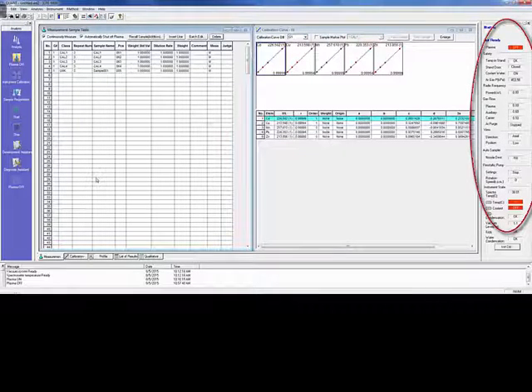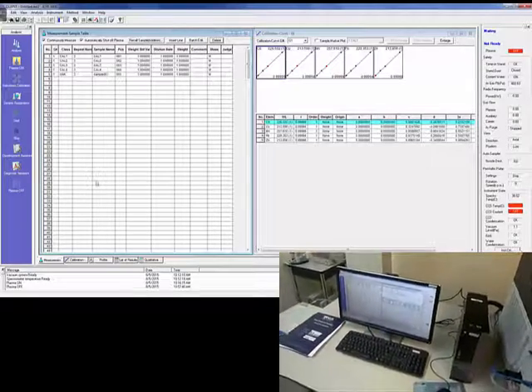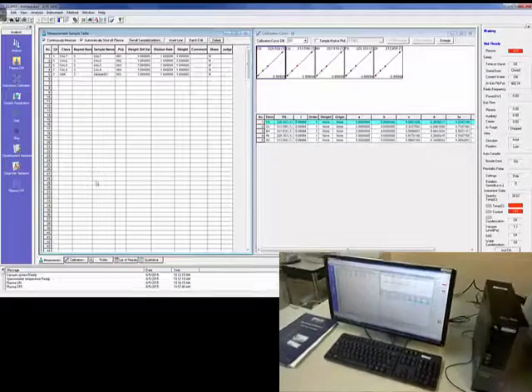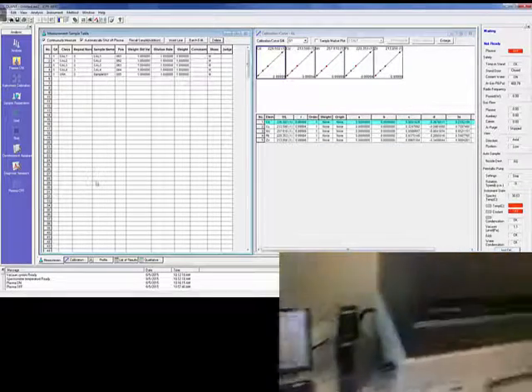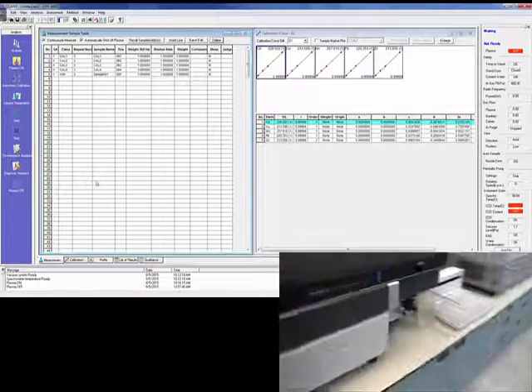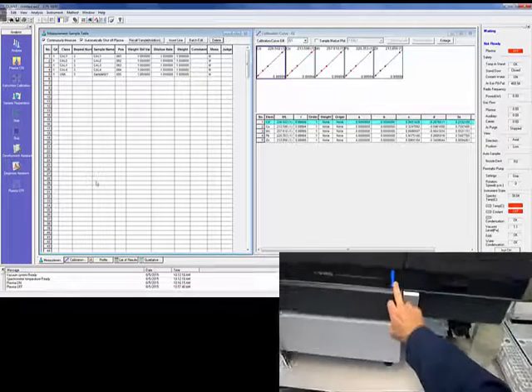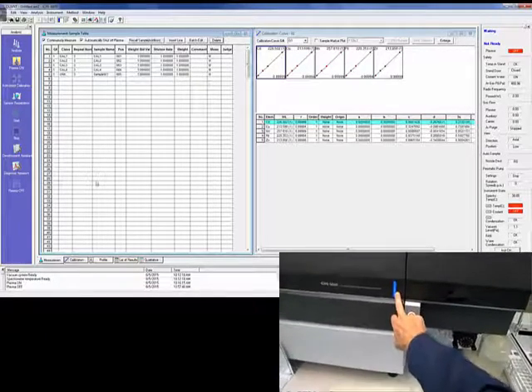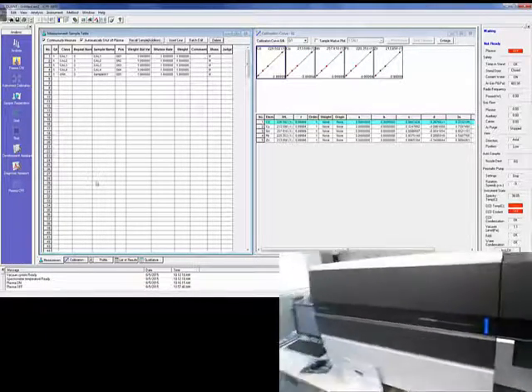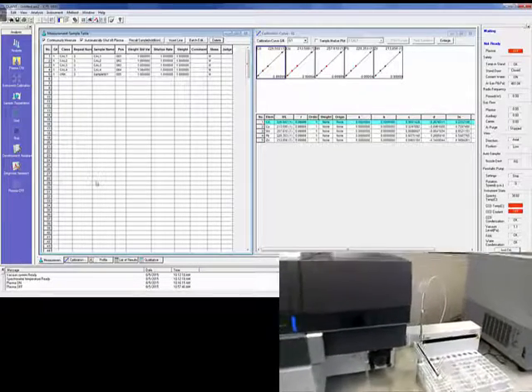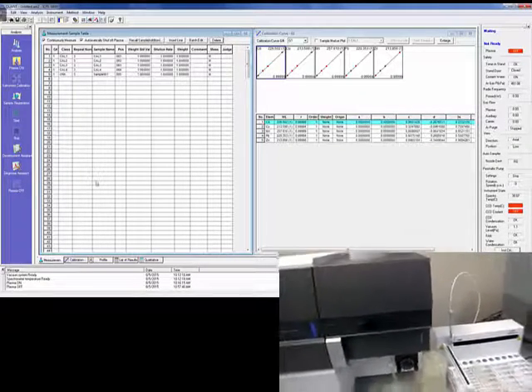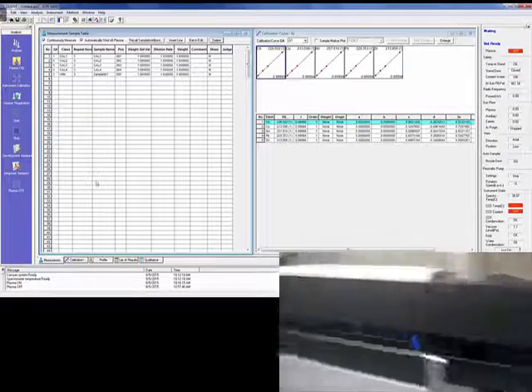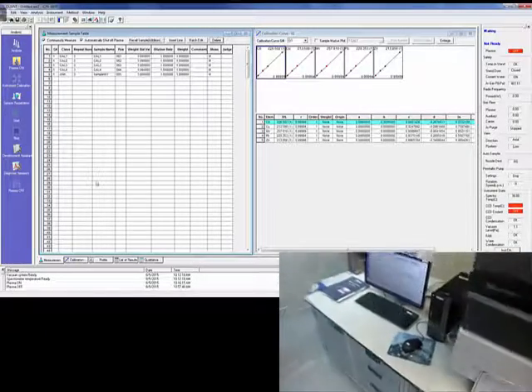Right, guys, we're back again and we should just look at the equipment. You can see that the light here is blue. Remember, we clicked to automatically turn off the plasma so that all of the samples and the standards have been analyzed. And now let's look at the results.